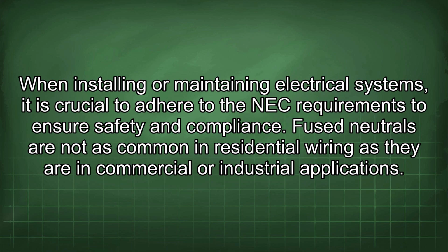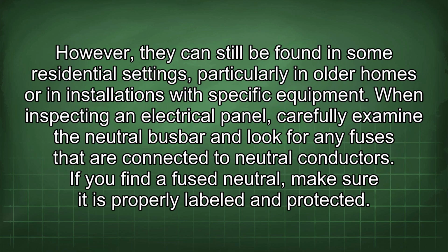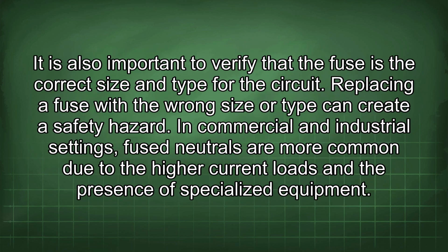Fused neutrals are not as common in residential wiring as they are in commercial or industrial applications. However, they can still be found in some residential settings, particularly in older homes or in installations with specific equipment. When inspecting an electrical panel, carefully examine the neutral busbar and look for any fuses that are connected to neutral conductors. If you find a fused neutral, make sure it is properly labeled and protected. It is also important to verify that the fuse is the correct size and type for the circuit. Replacing a fuse with the wrong size or type can create a safety hazard.